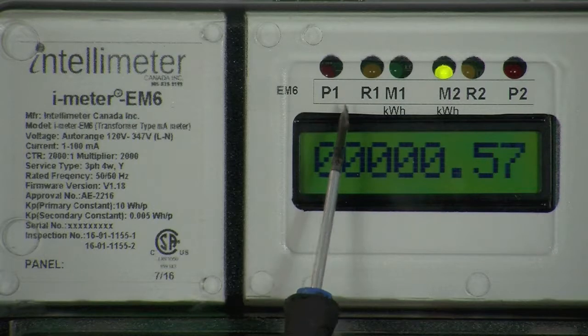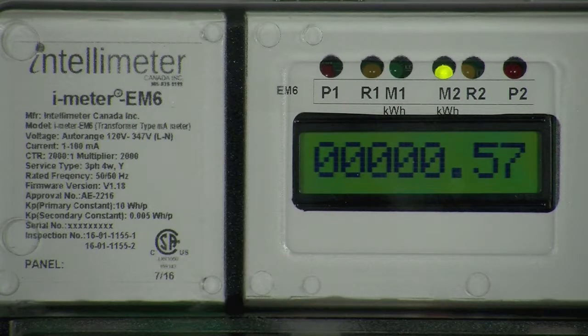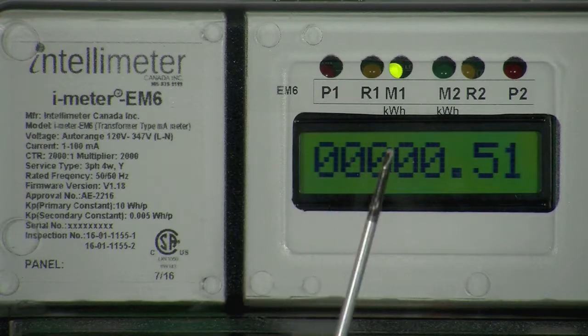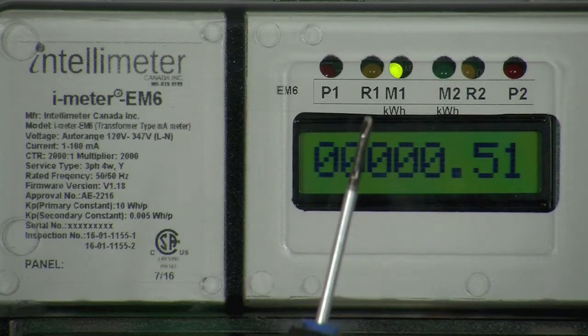Lastly, the amber LEDs marked R1 and R2 are reverse indicators. If either one or both of these LEDs are blinking, it means that there is a problem with the installation of one or more of the CTs or possibly the reference voltage. If R1 light is blinking, this means that there is an issue with one or more of the CTs for meter 1. If the R2 light is blinking, it means that there is an issue with one or more of the CTs for meter 2.